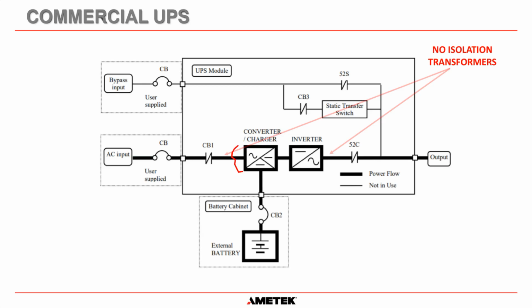Okay. And also what you find is the isolation that an isolation transformer gives you is if there is a failure in the battery charger, then it prevents the DC going back onto the AC at the distribution center, or the MCC that feeds the AC into the system. And that's a very bad thing if you get DC feeding back onto your AC supply. So if you know anything about transformers, you know that transformers cannot pass DC. So an isolation transformer gives you isolation between the charger and the AC input. And that is also the same if you have a transformer there. The inverter output, if there is some kind of failure in here and DC could somehow feed through that way there, the transformer would stop it. And it also helps with noise suppression as well.